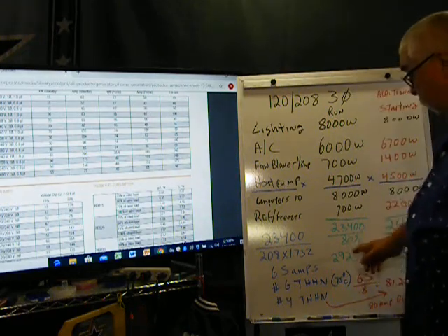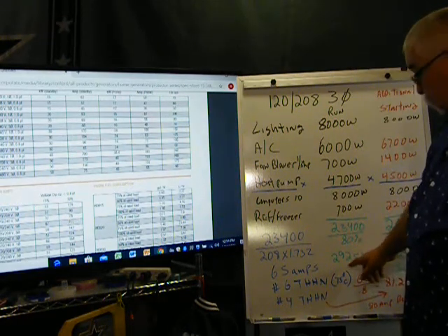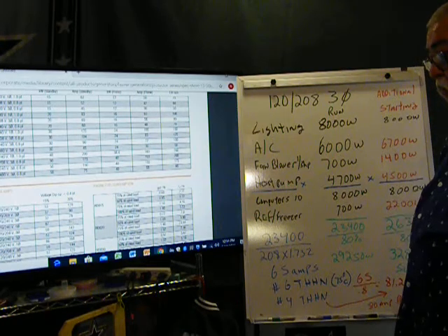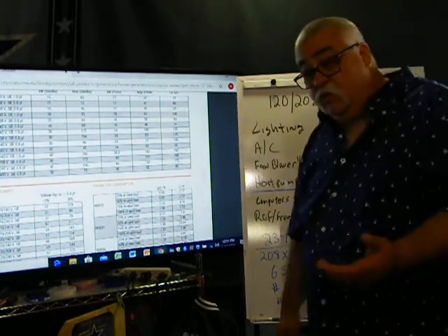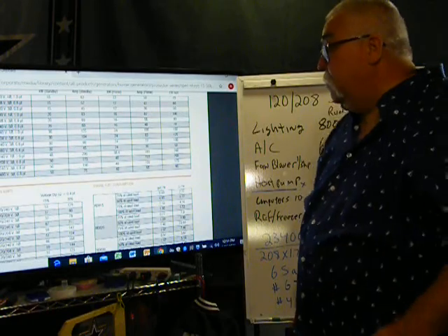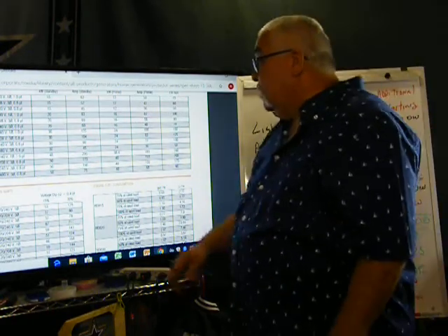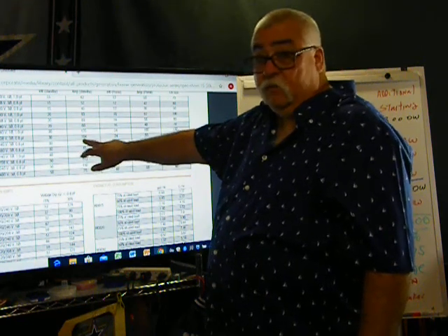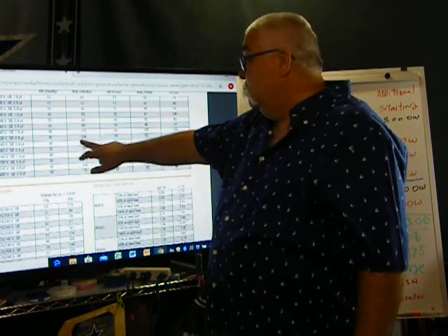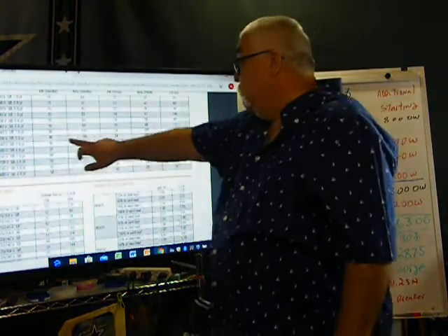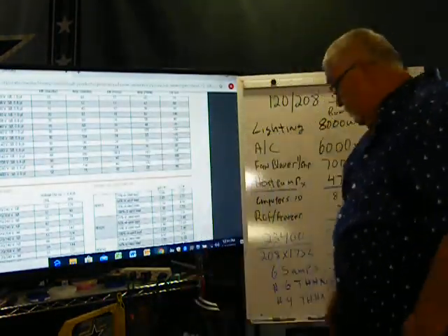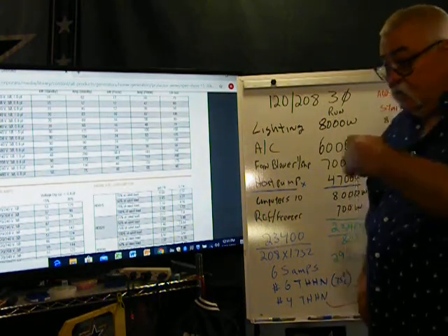That's why I divided by 80% to take me up. So that's where I'm using the 30 kW generator. That's what I will use, a 30 kW generator. So my wire size, I would need a number 2 because this generator does 104 amps. 120/208, 104 amps. Okay. Again, this is off the sheet.